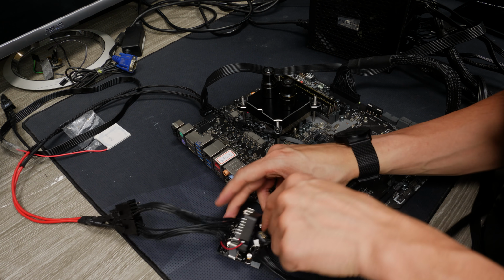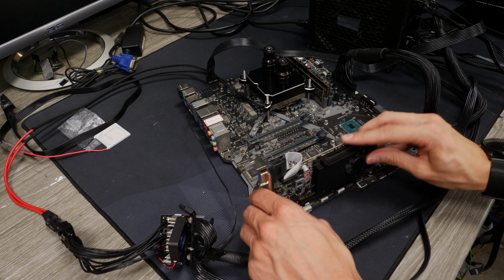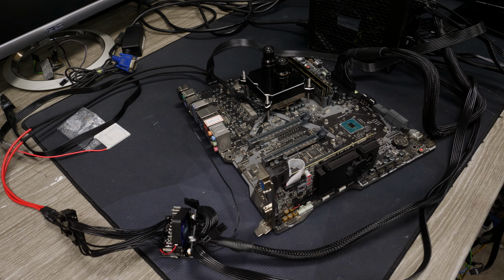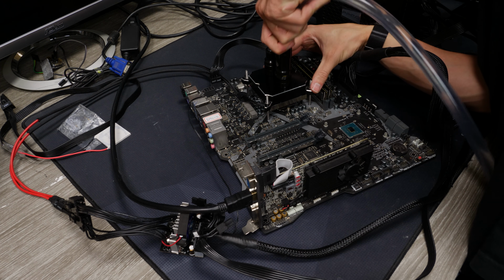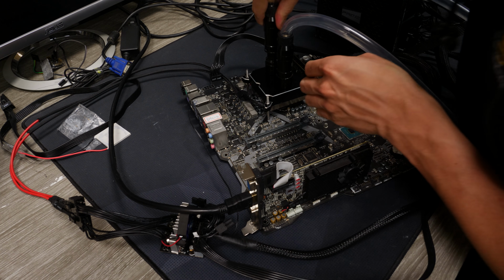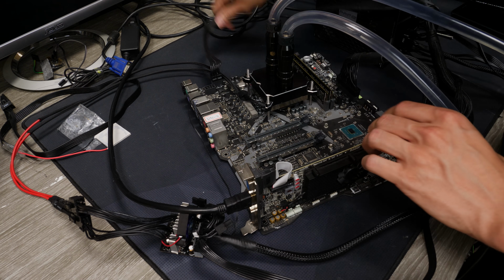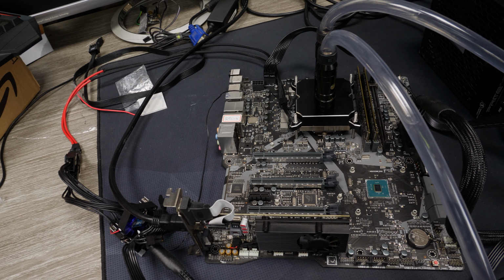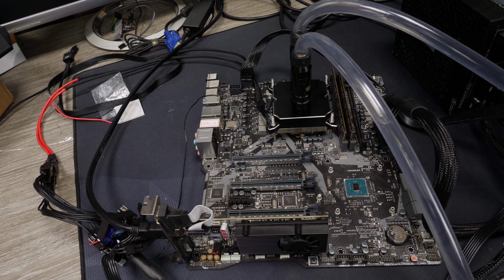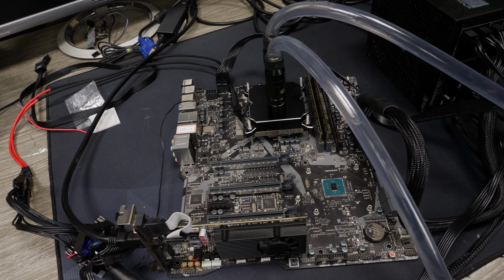The whole setup is then cooled by two 360 radiators, mainly needed because, as I said before, we have 360 watt power consumption of the TEC, and a peak power consumption of around 250 watt of the CPU. So total power consumption around 600 watt, which is quite a lot. We need around two 360 radiators to have a decent water temperature.